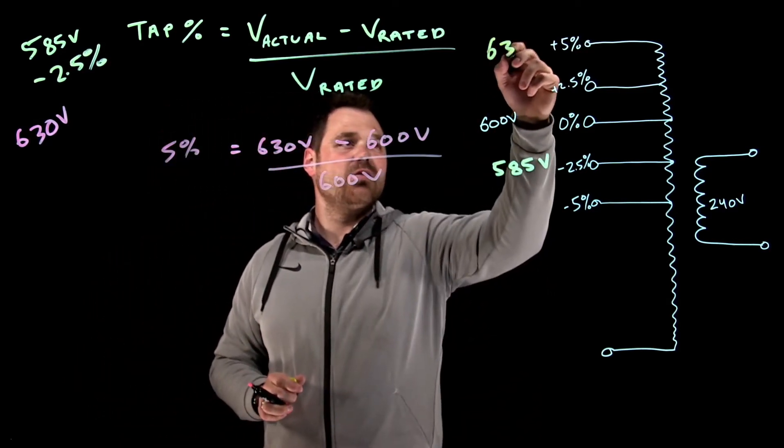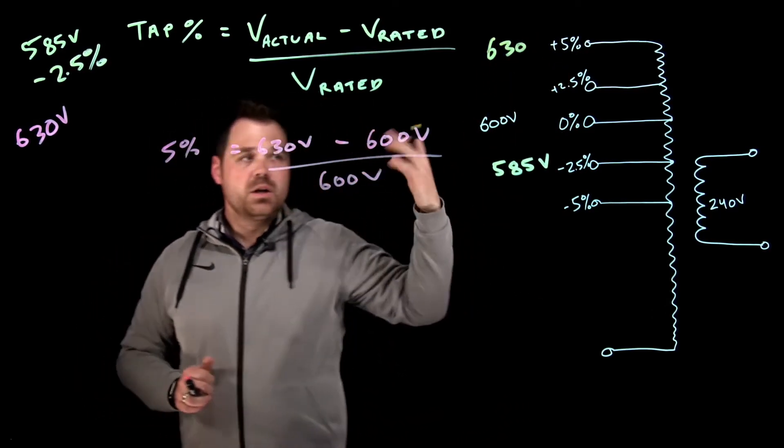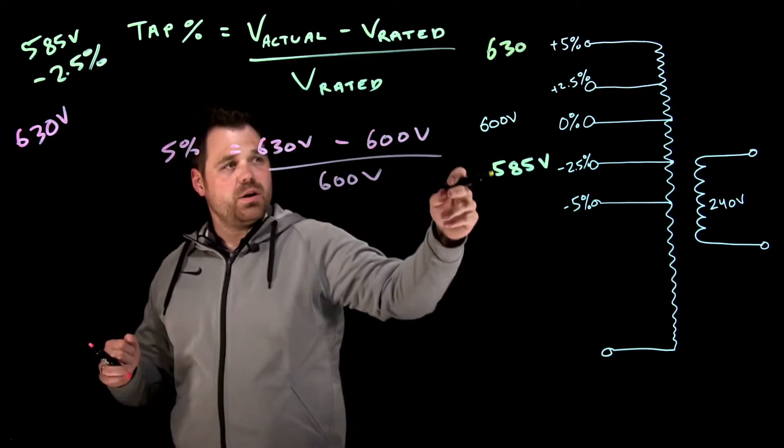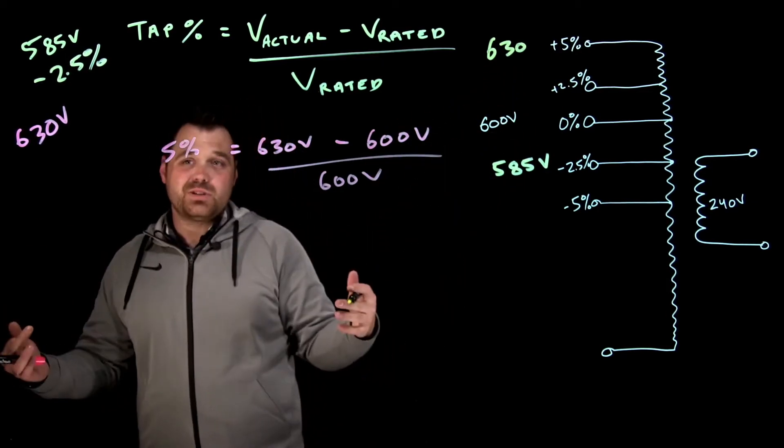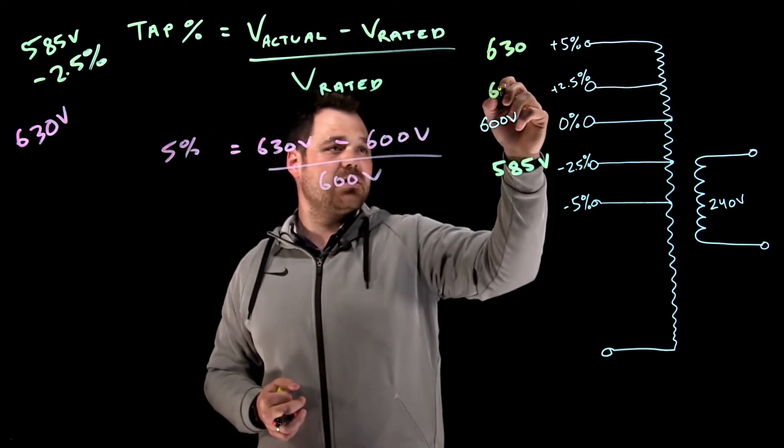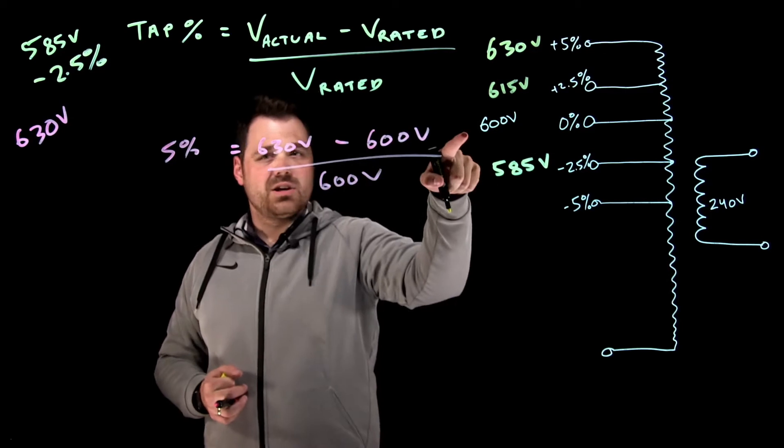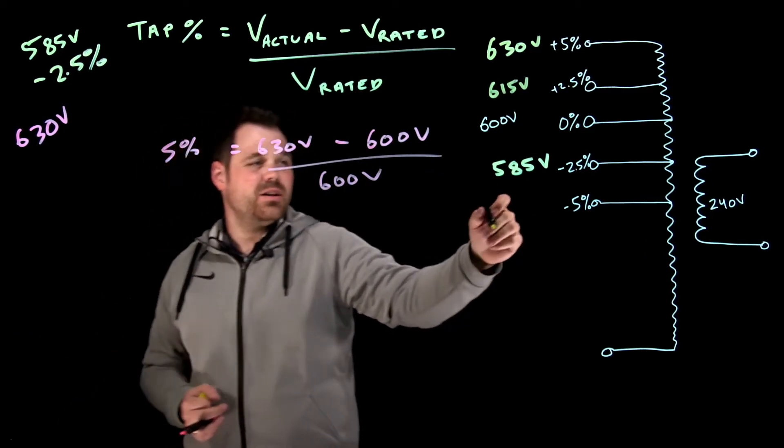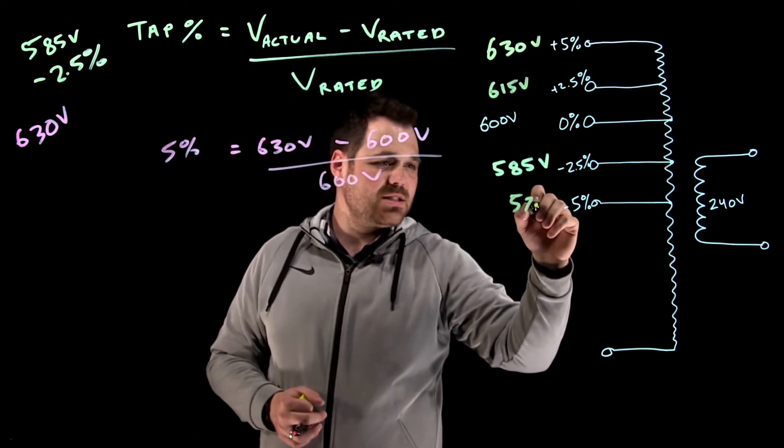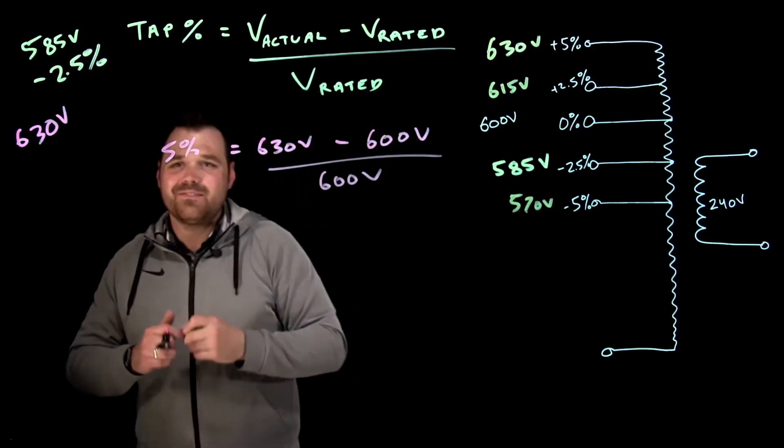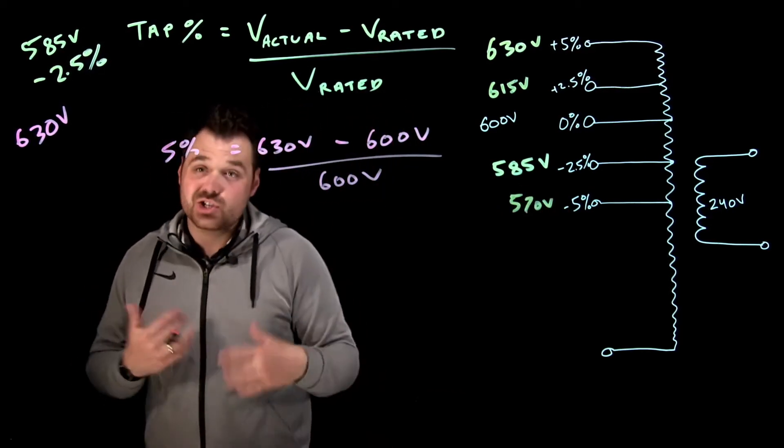So that's 630 volts up there. And then we could fill in the other two here just by going 600, or plus two and a half percent would give me 615 volts. And then 600 minus 5%, just type that into our calculator, gives us 570 volts. So we can kind of fill out the rest of that chart there.